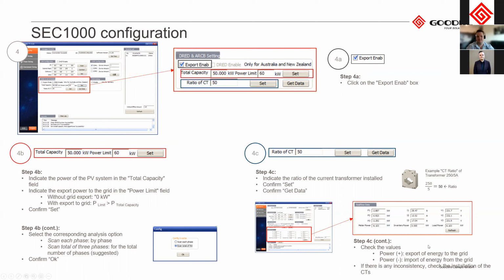So it's very important to check this when the grid, when your inverter power, is off. You can leave your inverters on, just don't have the AC to the inverter on yet. So we have the DC on our inverters on, we can confirm they're communicating well with our logger, but we do not put the AC to the inverters on yet. As you'll see here, we have the P1, P2, P3, that's the power rating. We need to make sure that these are all negative values. So for our site, negative is usage from the grid. It is very important that we make sure that this is correct.